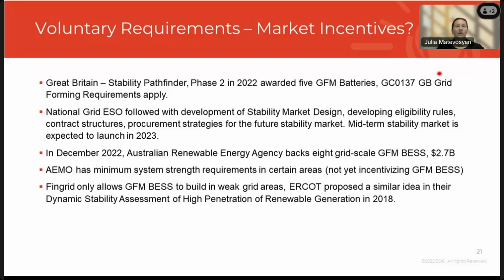And this is basically just a way to deploy this technology, get it piloted and learn more from multiple grid forming resources operating in the area. So it's not really incentivized by any kind of specifications or markets yet. AEMO has minimum system strength requirements in some parts of the grid. So you may think that would incentivize grid forming resources to come and provide system strength. But I think the holdup there is that apart from contribution of fault current, there is no good metric yet that is widely used to characterize system strength support from inverter-based resources. And so I think that's where grid forming cannot show its capability, because it can only provide maybe 1.5 at best per unit short circuit current.